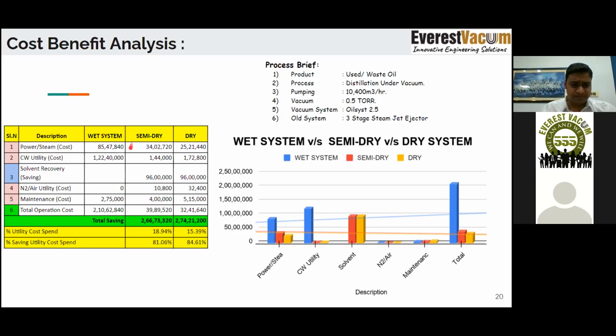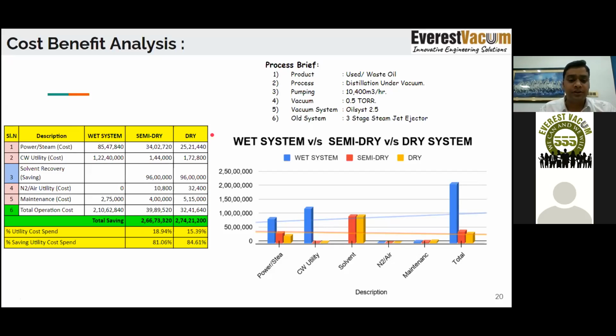So this is the comparison we are talking about with the semi-dry pumps. The oil assist vacuum pumps are consuming only 18.94%, equal to 19%, of the total operation cost of the wet system. So you save 81% of your operational cost by using Everest oil assist vacuum pumping systems over traditional pumps. Also, as Mr. Rakesh must have highlighted, Everest is manufacturing dry screw vacuum pumps in India and is the sole and first company in India to start it. Introducing dry vacuum pumps in replacement of these wet systems will help you save 84% of the total operation cost.